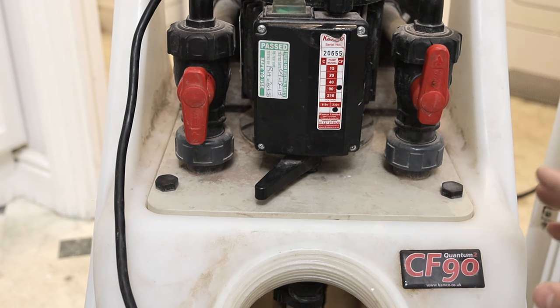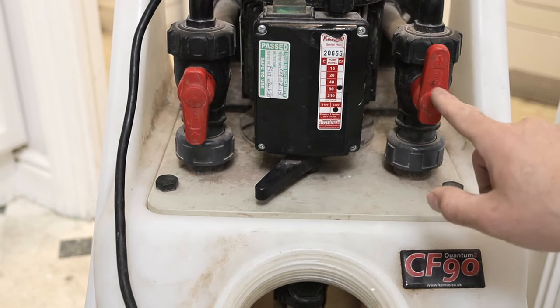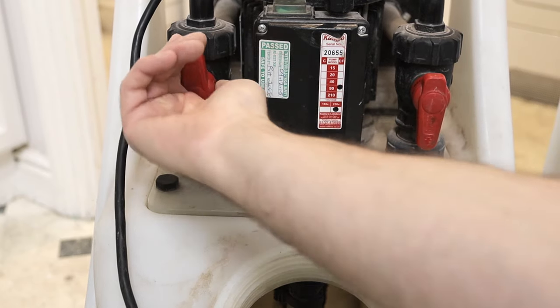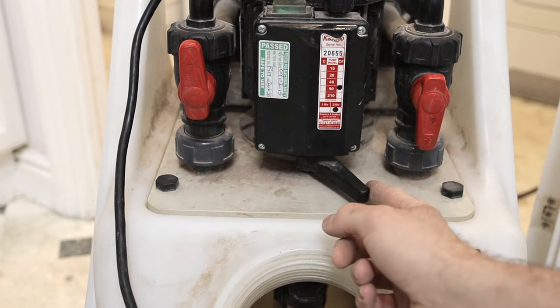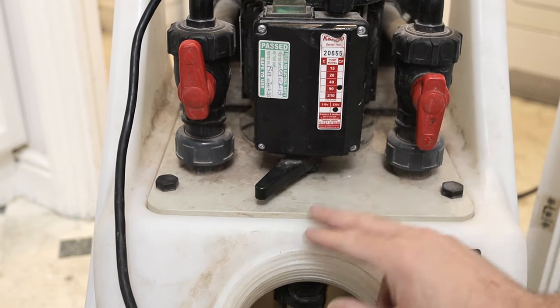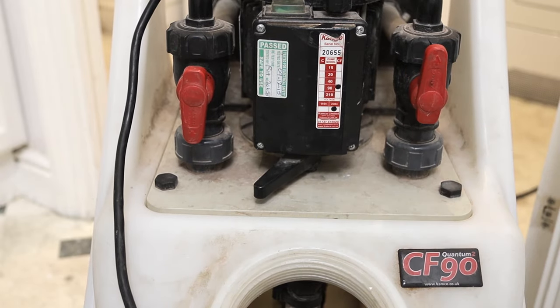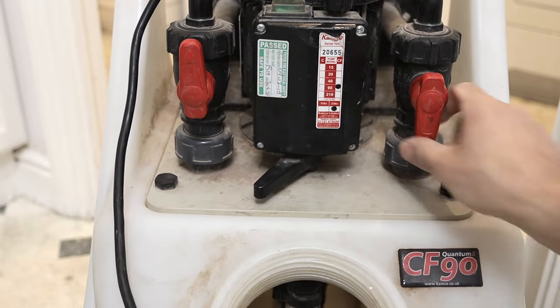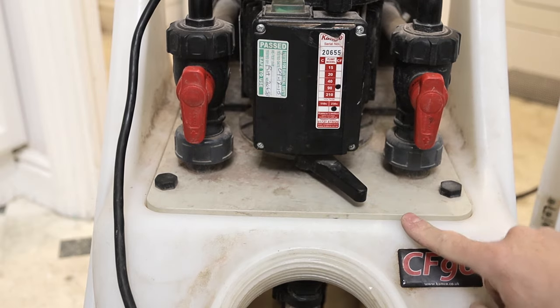When dumping water you really only have two valid positions. The direction of flow needs to go to the valve that points down and the other valve has to point up, or the reverse — valve points this way, water goes into the system through here and comes out through there. If you try to push against a closed valve nothing will happen; that setup doesn't work. With both valves pointing down, water recirculates — that works.